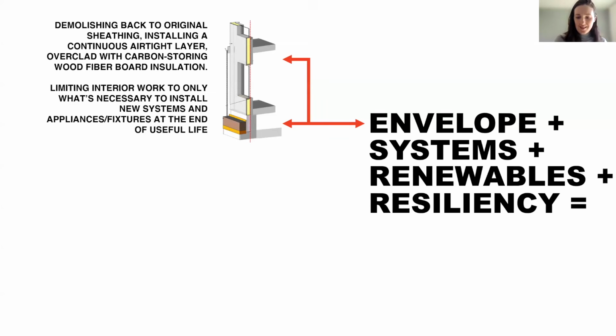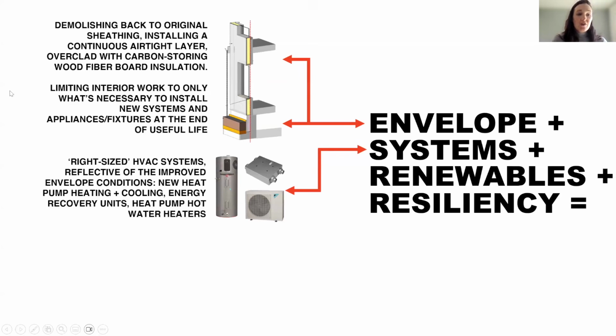For our systems, we're right sizing our HVAC to reflect the improved envelope conditions with thermal and air tightness improvements. For the first time ever, these buildings will have cooling—previously only window units existed. They'll get new heat pump technology for heating and cooling, energy recovery units for balanced ventilation, and heat pump hot water heaters for domestic hot water.